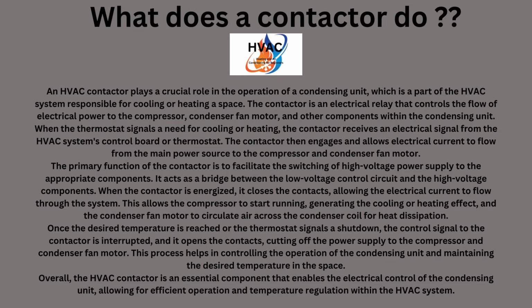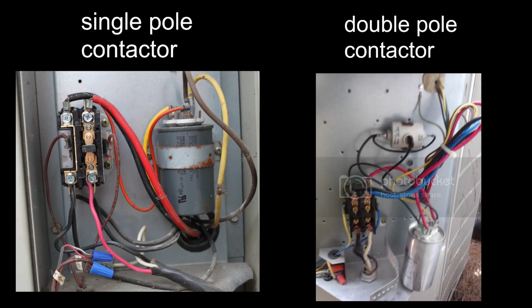So basically, what happens is when the 24 volts is fed to one side of the contactor, it allows it to engage the coil on it, introducing magnetism, pulls the contactor in, and then it allows the main voltage to feed through and energize the condensing unit for cooling operations and or heating if you have a heat pump. So let's go ahead and take a look at two different styles of contactor. One is called a single pole, the other one's called a dual pole. So let's kind of go into the aspect.